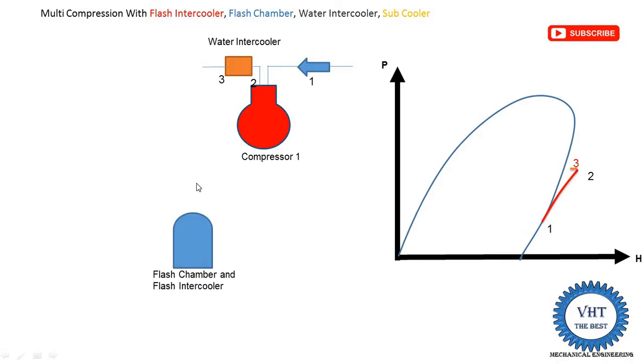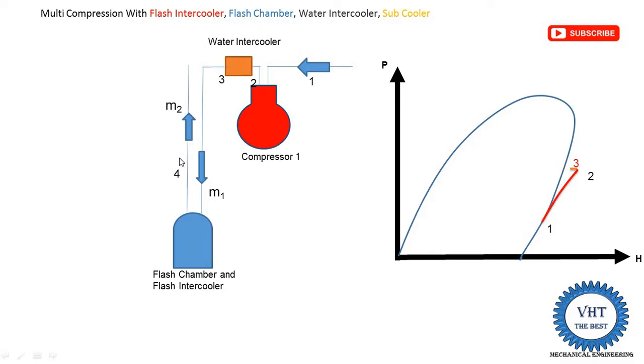Then refrigerant is supplied into the flash intercooler or flash chamber. Flash means it is a partially saturated vapor coming out from the expansion device. Intercooler means it reduces the temperature of refrigerant between the two compressors. With the help of this partially saturated vapor, we reduce the temperature of refrigerant coming out from the water intercooler, whose mass is M1. Point 3 is superheated, so it is converted into saturated vapor after cooling. The mass M2 is the mass of refrigerant coming out from the intercooler, supplied into the high pressure compressor at point number 4. Point 4 is on the saturation line at intermediate pressure.